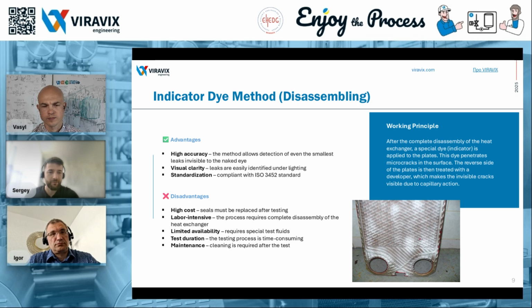The main advantages of this method are its high precision, allowing detection of even the smallest leaks, and its strong visual clarity. The results are immediately visible to the eye. There is also an ISO standard for this method. However, one of the main disadvantages is that after the test, new gaskets must be installed in the heat exchanger. This significantly increases the overall cost of the method, since new gaskets are quite expensive. Labor-intensive process.